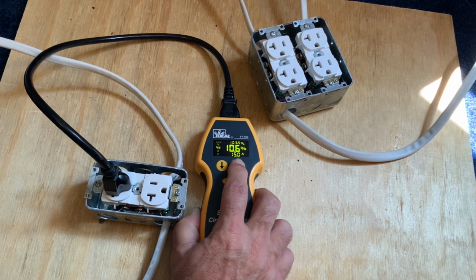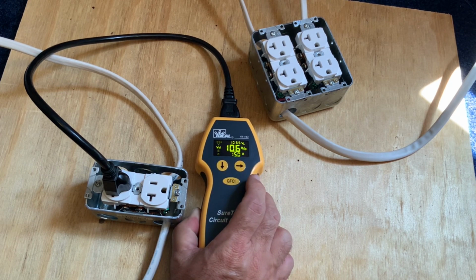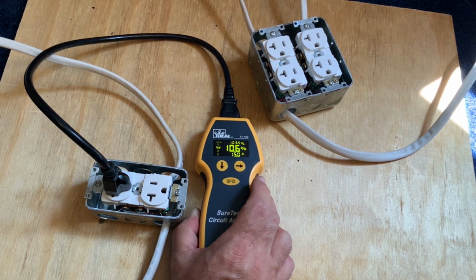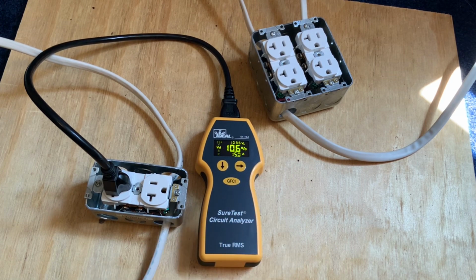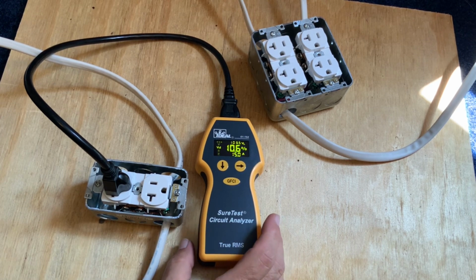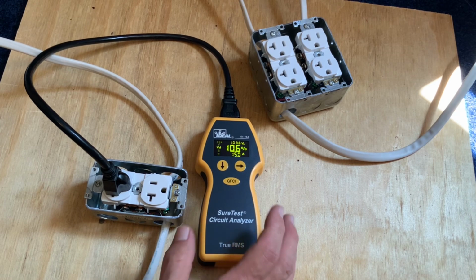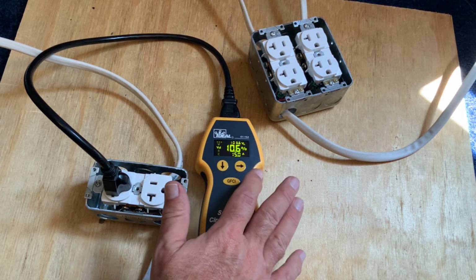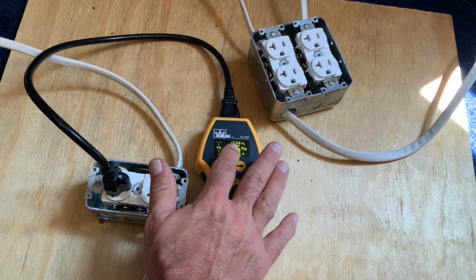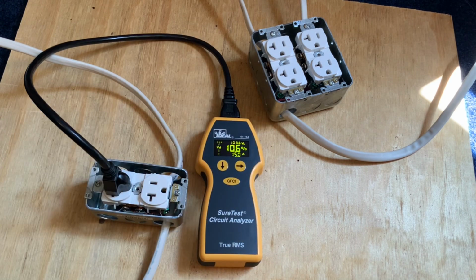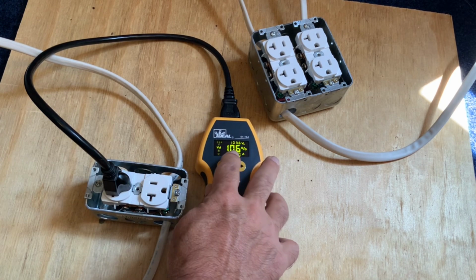to that outlet. If you had something plugged in that was drawing 15 amps, now that would be 12.34 volts dropped on that wiring in your house, which means that your voltage drops 10.6% at the outlet. The NEC recommends that you don't have any more than a 5% drop on any outlet, and your wiring should be big enough to accommodate that. It's got to be hard to find a lot of homes where all of the outlets would meet a 5% drop with a 12 or a 15 amp load.